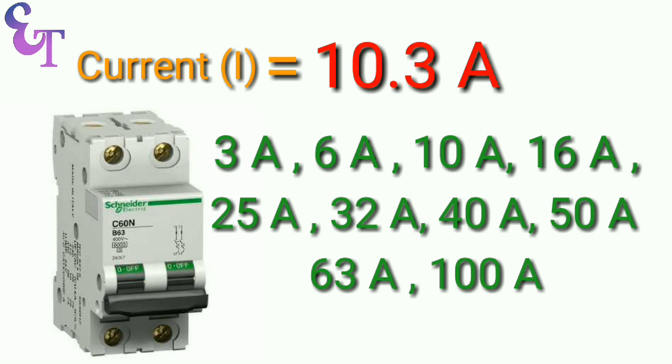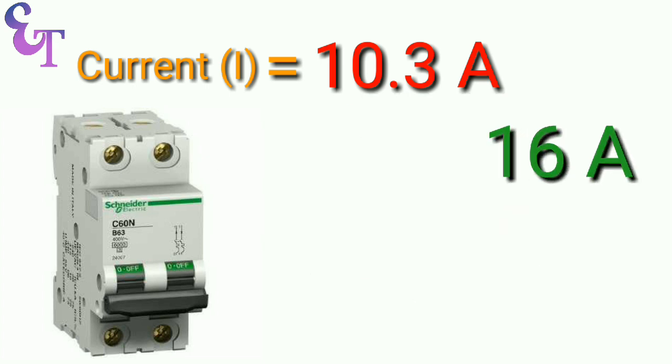Our total load current is 10.3 ampere. We have to select a few amperes bigger rating MCB, so we will select 16 ampere MCB.